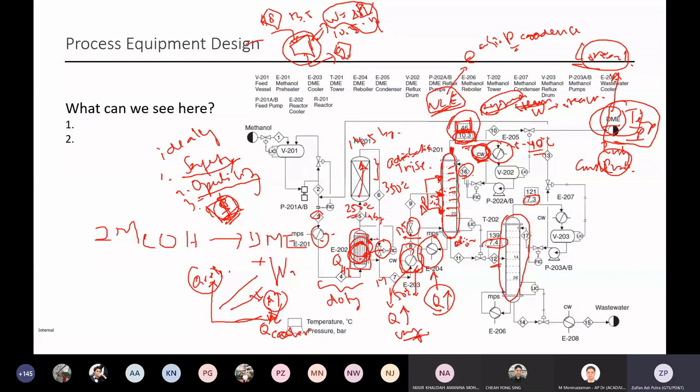And then you might wonder, okay, if I'm cooling it with the same cooling water, then I can, for example, get a lower pressure than this number in such a way that this line I can condense at the same 40-50 degrees C, right? From 45 to 50 degrees C, because you are going to save, using the same 35 to 40 degrees C cooling water. So why would the person who wrote this book want to condense it at 7.3 bar and 121 degrees C?